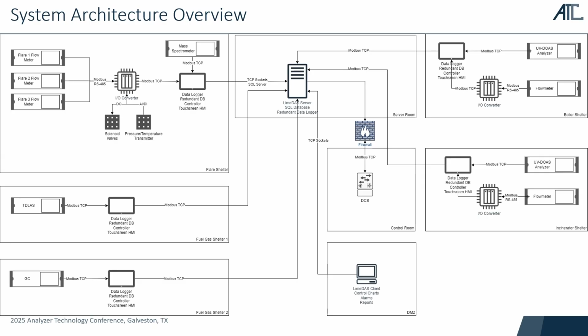Each has its own dedicated data collection unit, which then are all centralized in a central DAS server, which has an SQL database. It has a redundant data collection unit. Because it's software-based, now you can have a standby mode on the central server. So if the main data collection unit computer were to fail in the shelter, a backup one would be communicating with all the analytical equipment. And then once the main one is restored, the data is automatically synced back up. And all the raw data is stored for the lifetime of the project.